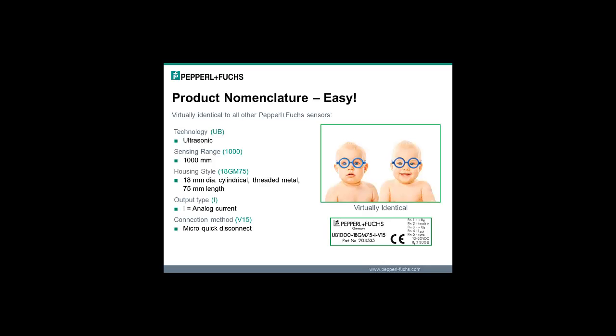I is universal, whether it's an analog or a photo eye, or that means it's an analog output. And then the connector. These use the same type of connectors that all Pepperl+Fuchs sensors use. So V15 is a 5-pin micro quick disconnect. That's a quick look at the nomenclature, but if you know the inductive nomenclature, you pretty much automatically know the ultrasonic nomenclature.